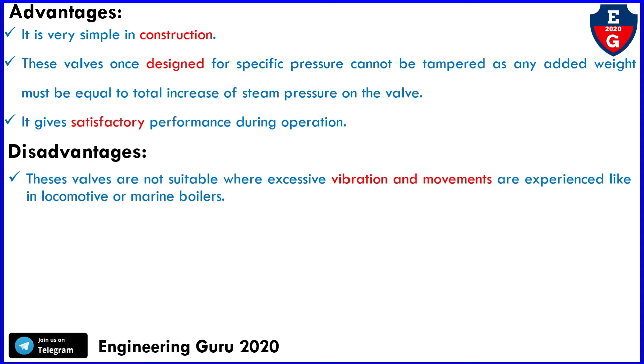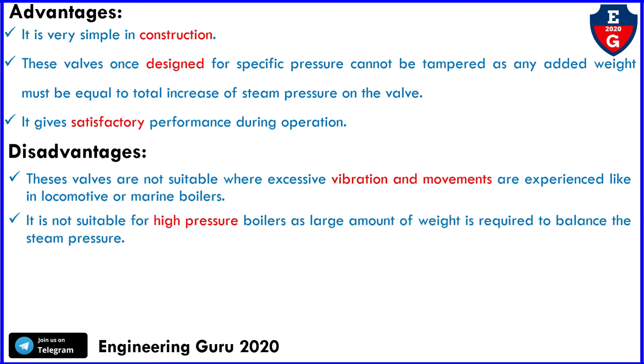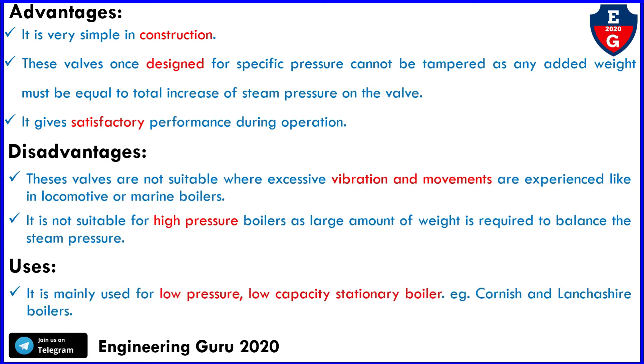Disadvantages: this valve is not suitable where excessive vibration and movements are experienced, such as in locomotive or marine boilers. It is also not suitable for high pressure boilers, as a large amount of weight is required to balance the steam pressure. Uses: it is mainly used for low pressure, low capacity stationary boilers — for example, Cornish and Lancashire boilers.